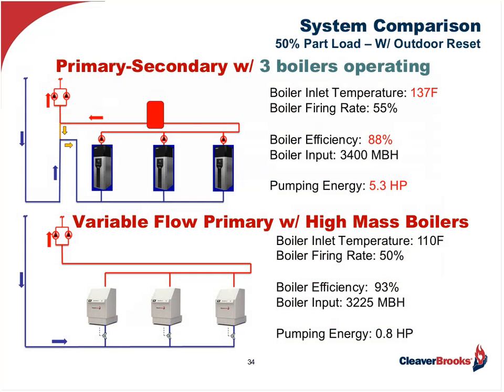Now somebody might say, well, what if we run all 3 boilers at a lower firing rate? You might think that would help because of that firing rate curve, but in reality it works against you on 2 counts. First off, you now have 300 GPM in that primary loop, so you're going to have more mixing in the decoupler, and your inlet temperature goes up from 130 to 137. That hurts your efficiency, even though your firing rate has gone down. We're now down at 88% efficient because we're no longer in the condensing mode. Secondly, I'm now running 3 pumps that are constant speed, so I've just increased my pumping horsepower. So one of the takeaways, when you're running primary-secondary, you want to run as few boilers as possible, versus variable flow primary, you want to run as many boilers as possible.